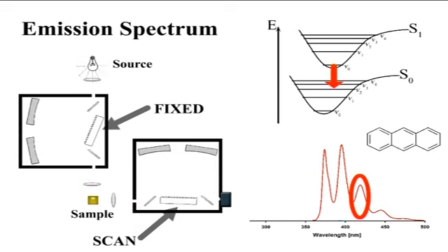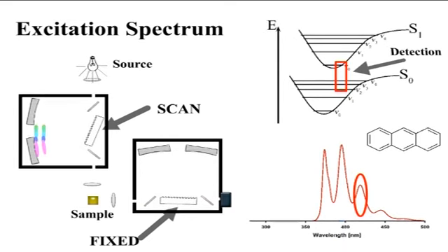However, the detector unavoidably receives some of the incident radiation as a result of the inherent scattering properties of the solutions themselves or if dust or other solids are present. Filters are used to eliminate this residual scatter. The primary filter selects short wavelength radiation capable of causing excitation of the test substance, while the secondary filter is normally a sharp cut off filter that allows the longer wavelength fluorescence to be transmitted but blocks the scattered radiation.